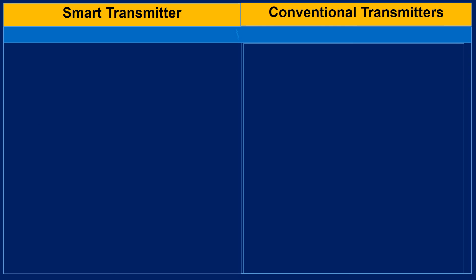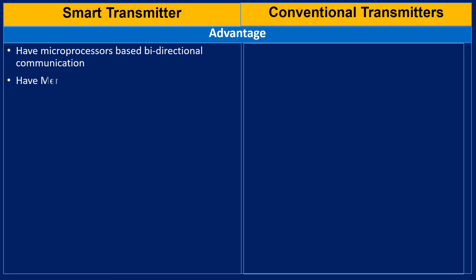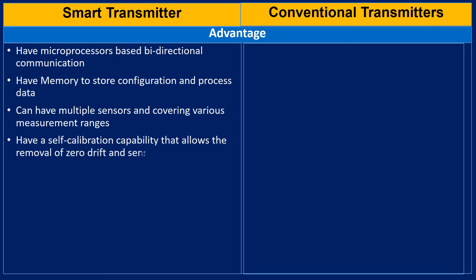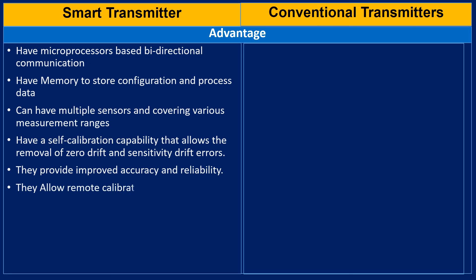The advantages of smart transmitters include: microprocessor-based bidirectional communication, memory to store configuration and process data, support for multiple sensors covering various measurement ranges, self-calibration capabilities that allow removal of zero drift and sensitivity drift errors, improved accuracy and reliability, analog and digital communication on two-wire loops simultaneously, and improved turndown ratio and stability.